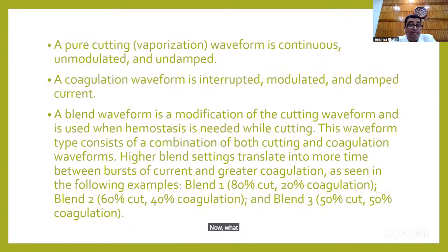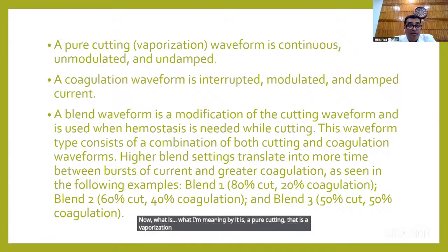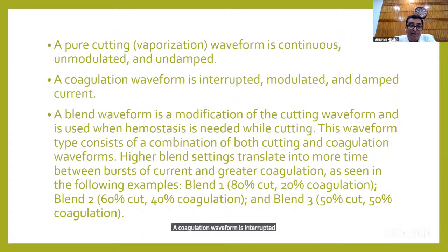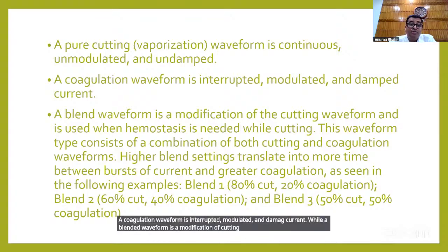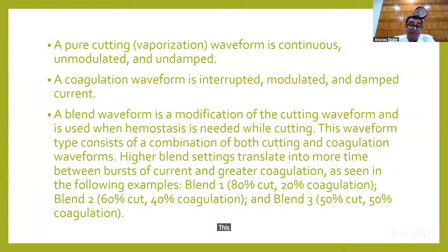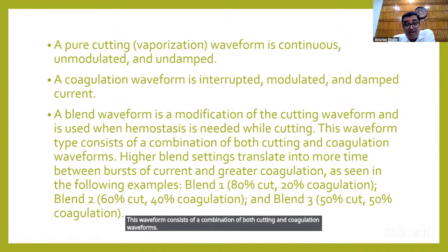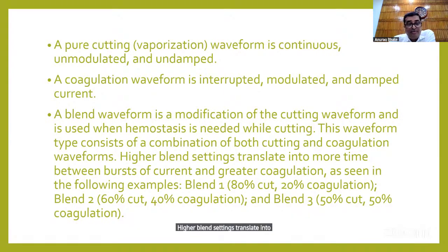Now, what I mean by it is, a pure cutting waveform, that is a vaporization waveform, is continuous, unmodulated, and undamped. A coagulation waveform is interrupted, modulated, and damped current, while a blend waveform is a modification of the cutting waveform and is used when hemostasis is needed while cutting. This waveform consists of a combination of both cutting and coagulation waveforms. Higher blend settings translate into more time between bursts of current and greater coagulation, as seen in the following example.